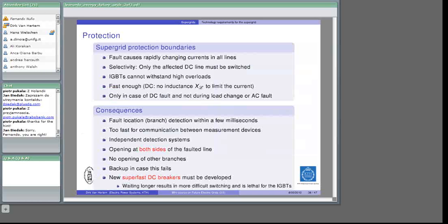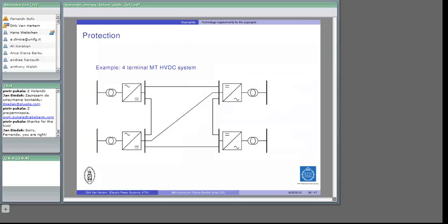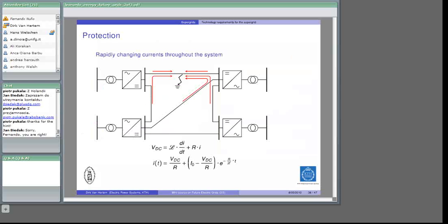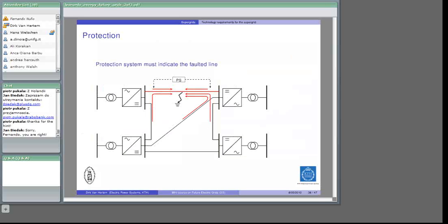I will just show very quickly, because I see that I'm running out of time, how the protection is done. Let's consider this 4-terminal DC system where somewhere a fault is happening. This fault will cause all the currents to go to that point, and you will have a big overload, and of course you want to isolate this problem. What happens is that the protection system needs to determine, okay, it's this line that's actually faulted, and this is done by measurements locally there without communication, and then the correct transmission line should be opened. This all within, let's say, 5 milliseconds.